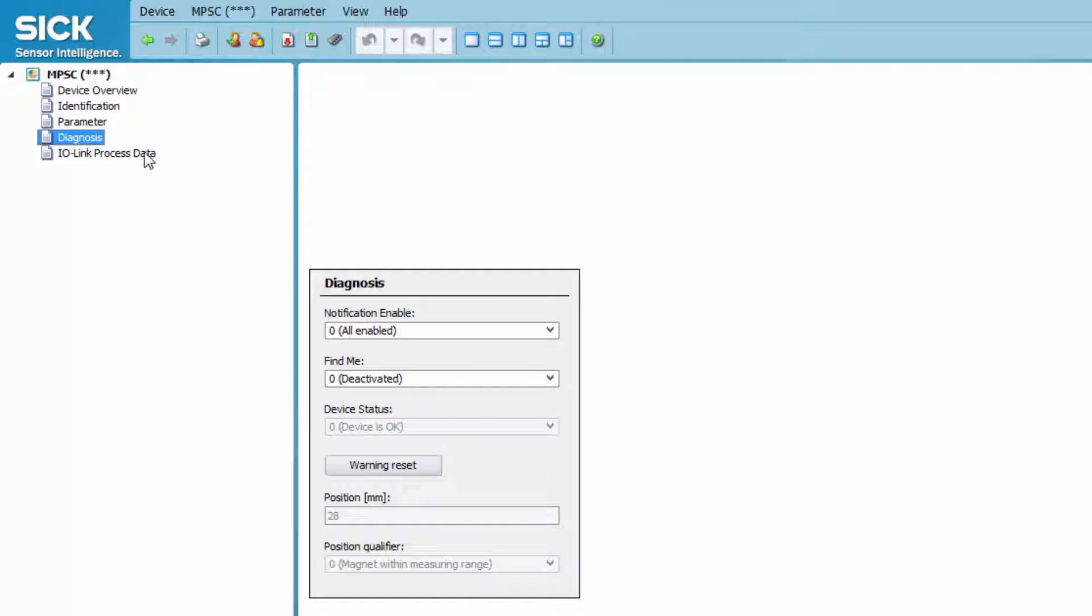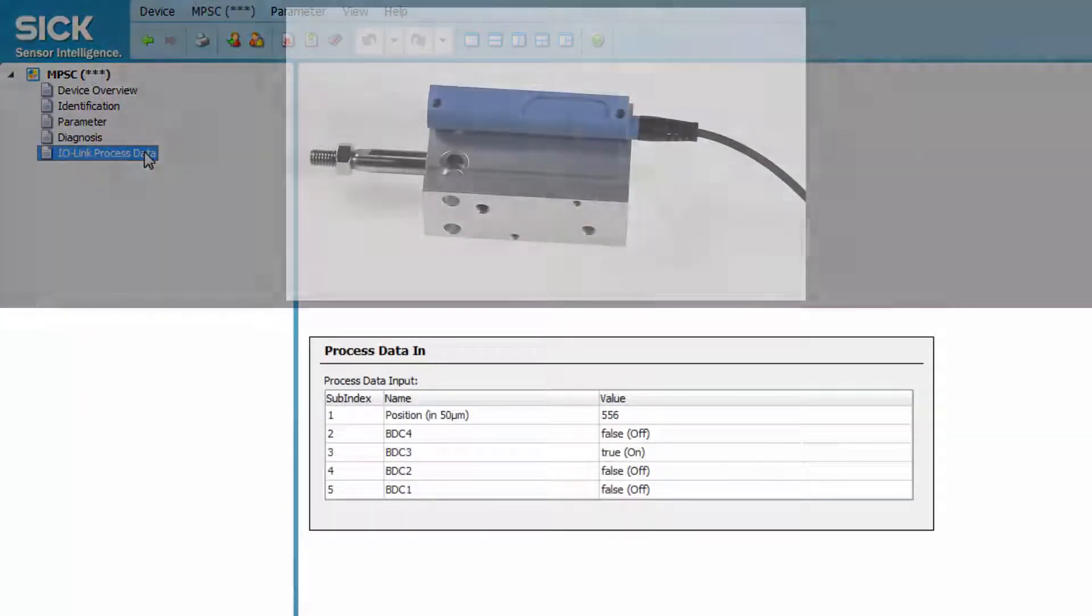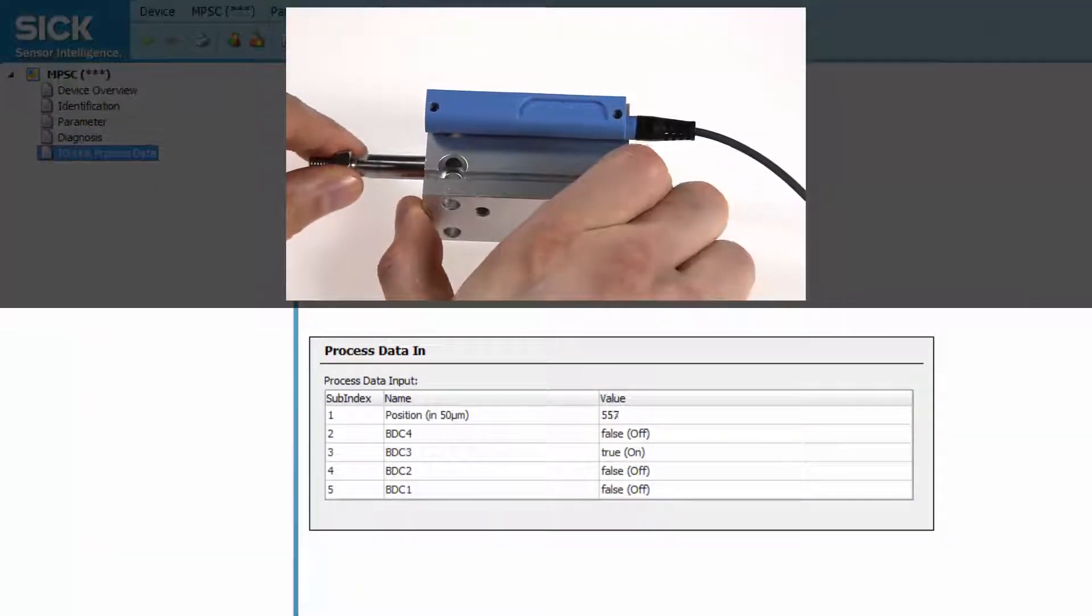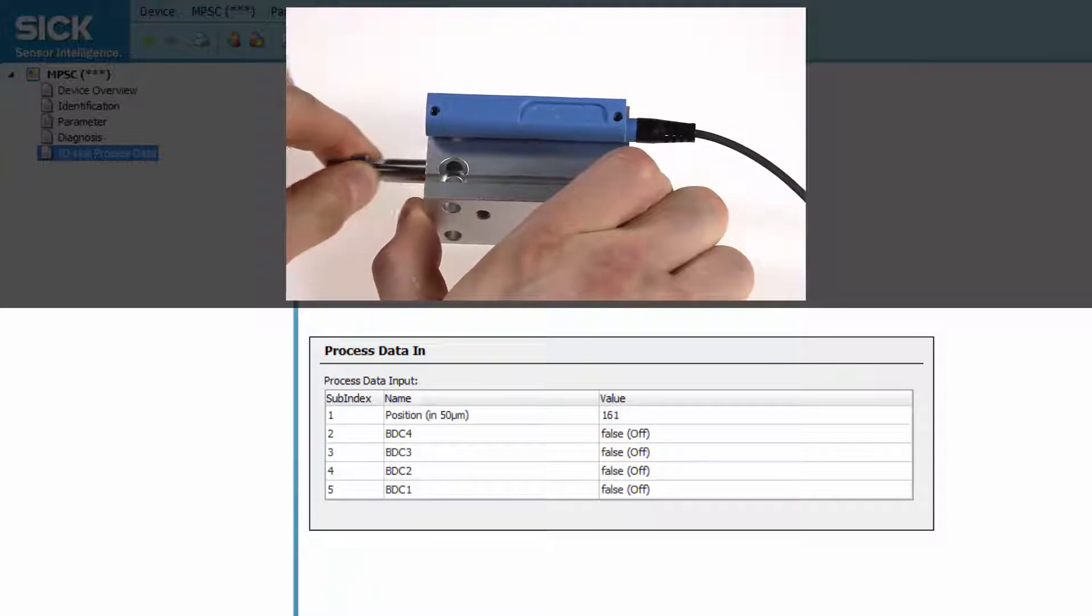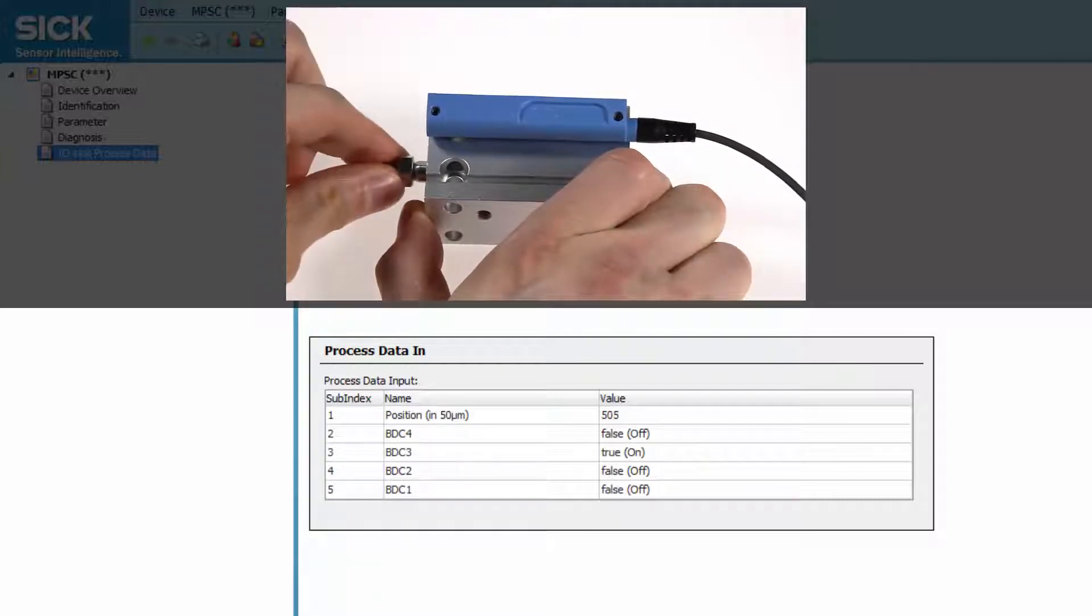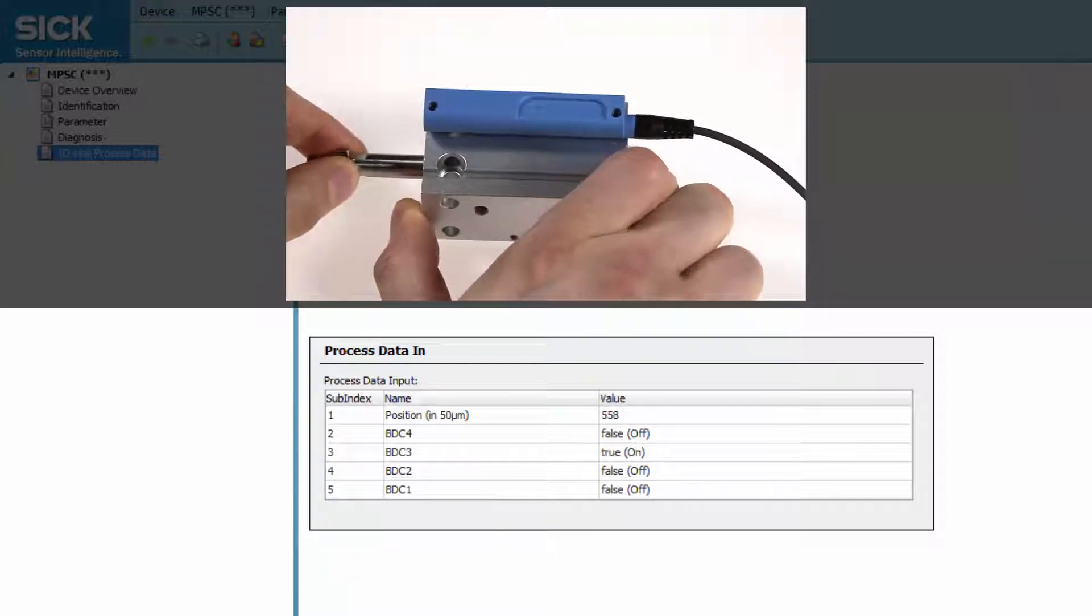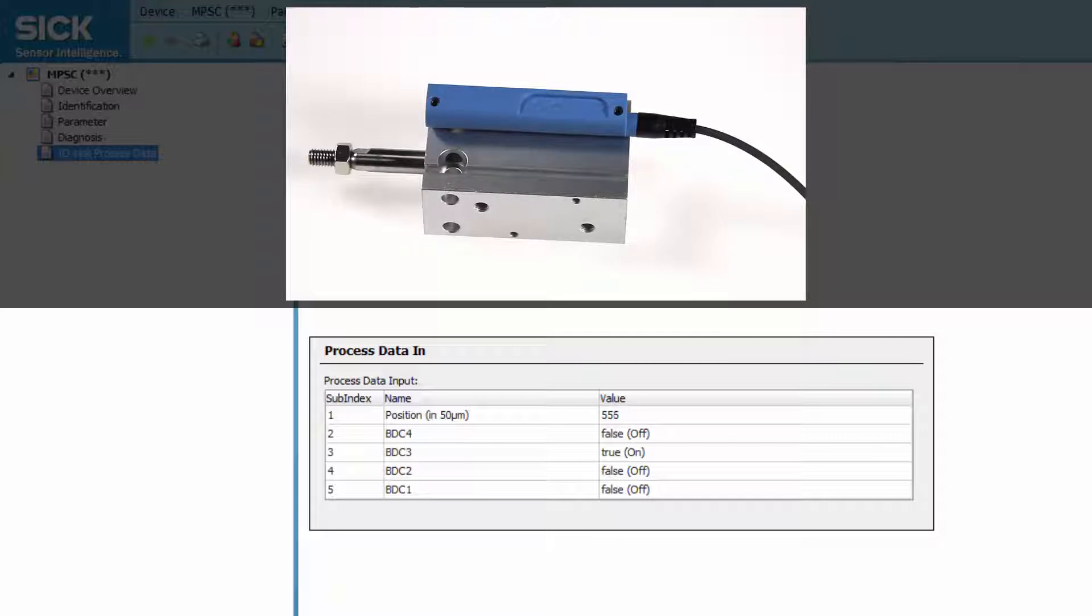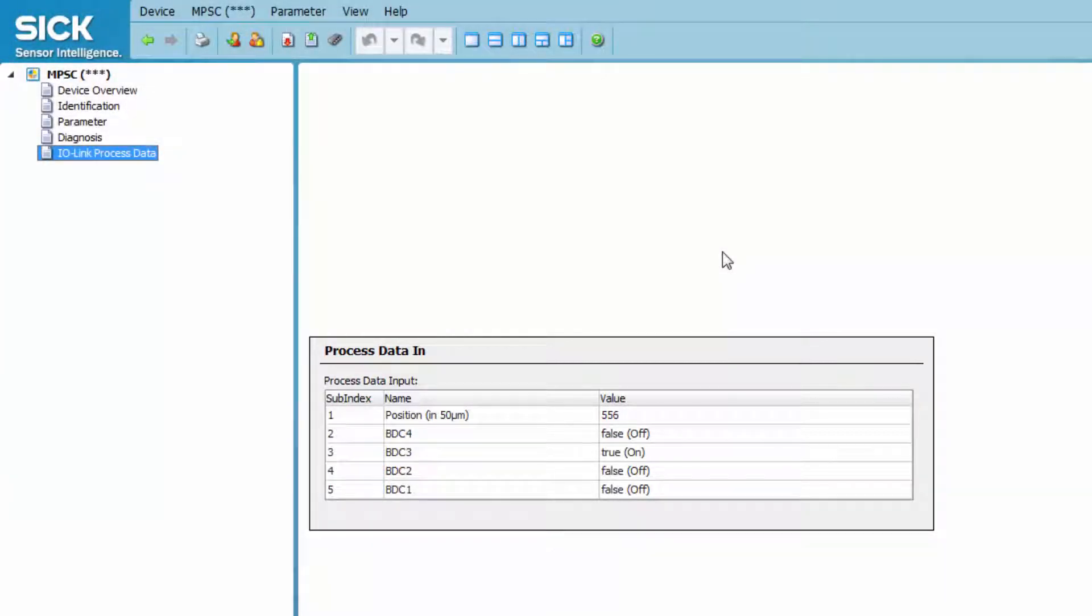The IO-Link Process Data tab shows the current position of the piston in relation to the beginning of the sensor housing on the plug side. The value displayed is the distance in 50 micron, which is the accuracy of the sensor. In order to get the value in millimeter, it needs to be multiplied with 0.05. The Teach In of the range has no influence on the values as it is the raw data of the sensor. This tab also shows the current status of the BDCs, so if a switching output is active or not.